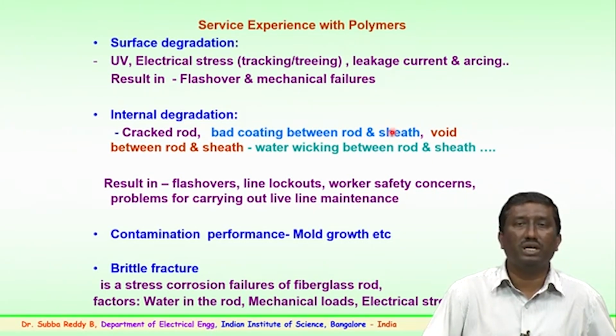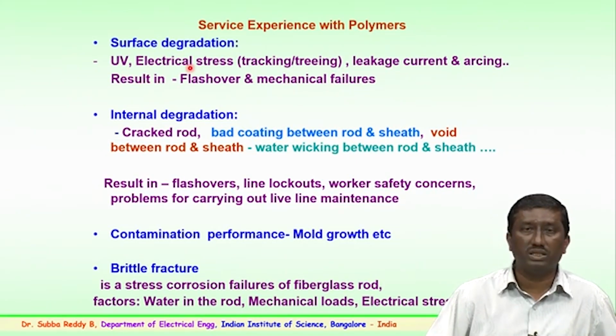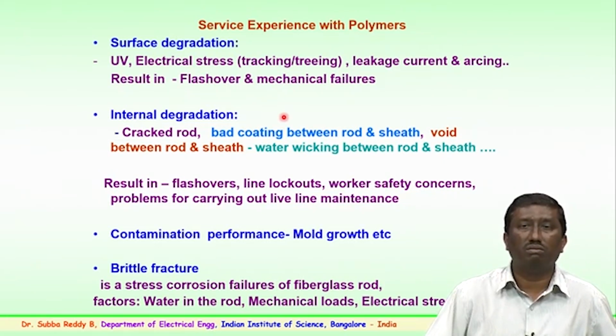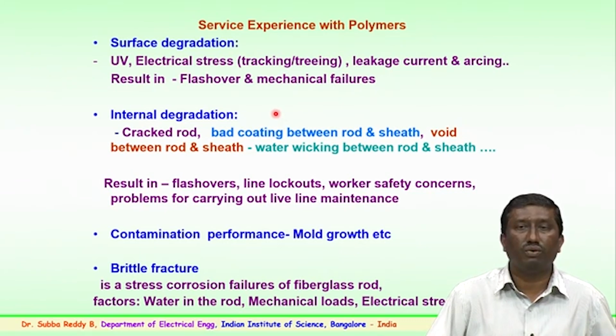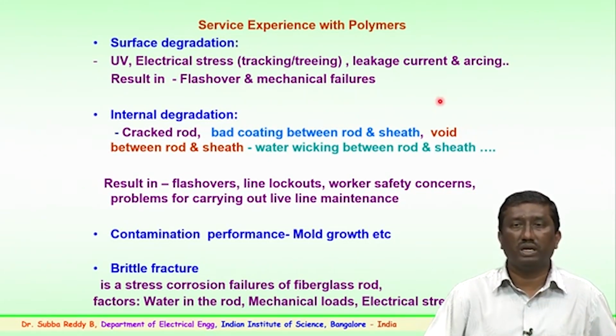phase in the field. So, surface degradation is the important aspect. The surface degradation may be caused by ultraviolet rays, because of the sun, or from the corona of the hardware which we mentioned. Continuous electrical stress on the insulator over a period of time could cause tracking or treeing. Tracking or treeing is again the slow failure of the insulator surface, where tracking could occur and the insulator could see leakage current flows and degradation of the material could happen. So, this tracking or treeing of the surface could happen over a period of time because of the electrical stress, wherein the leakage current and small arcings, known as partial arcing or scintillations, could happen, which could result in flashover and sometimes mechanical failures because of the surface degradation.